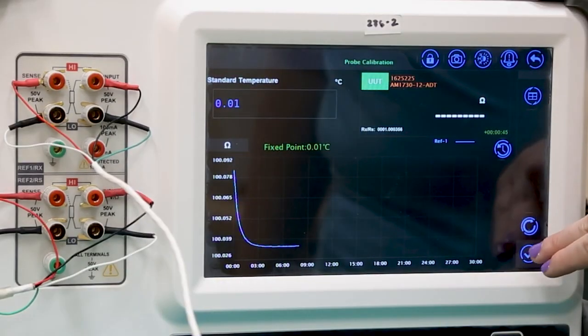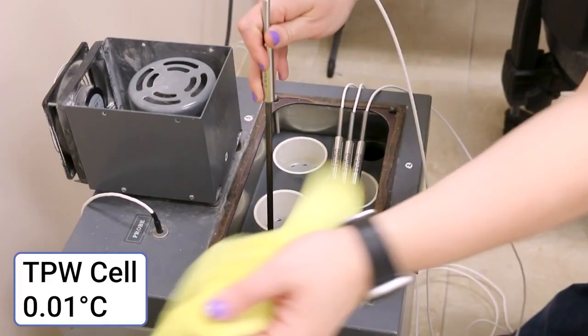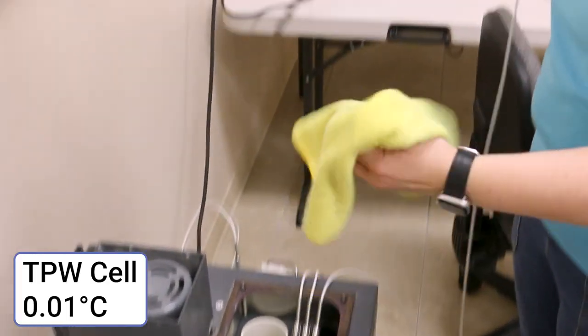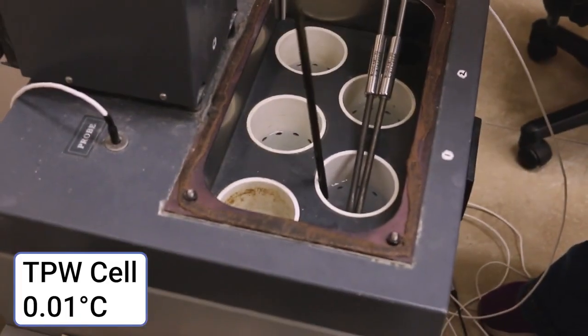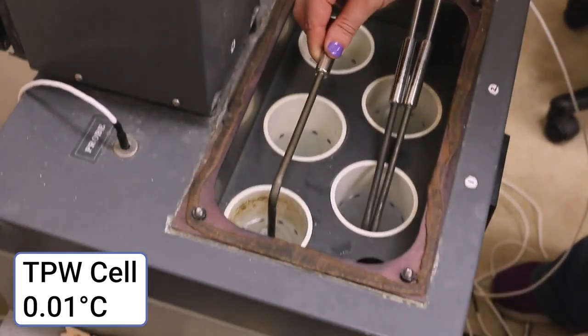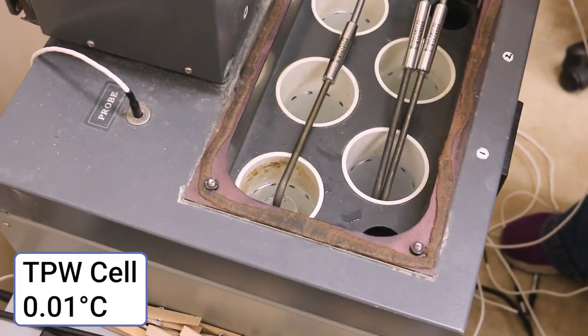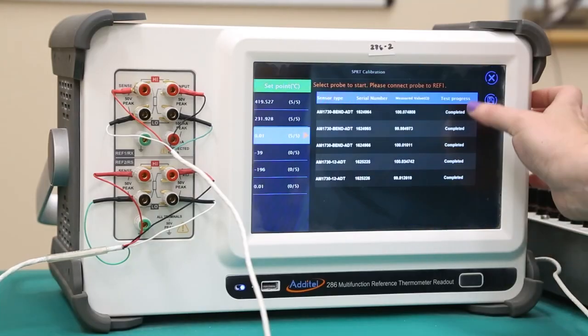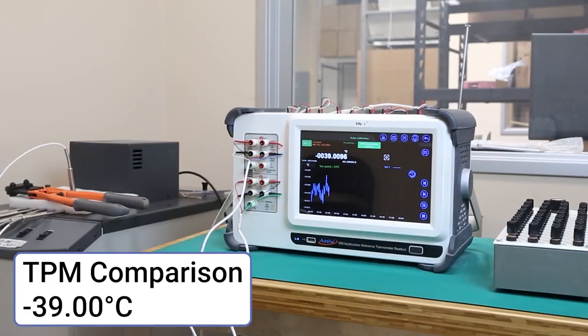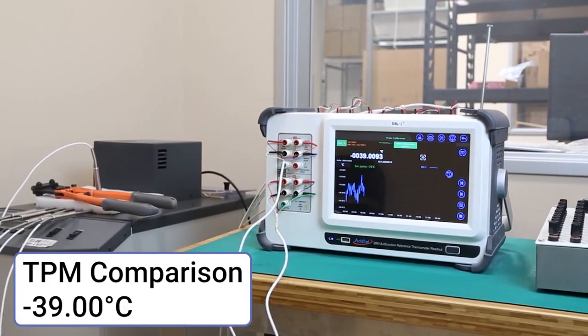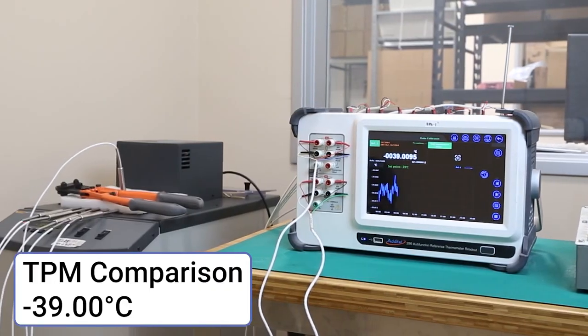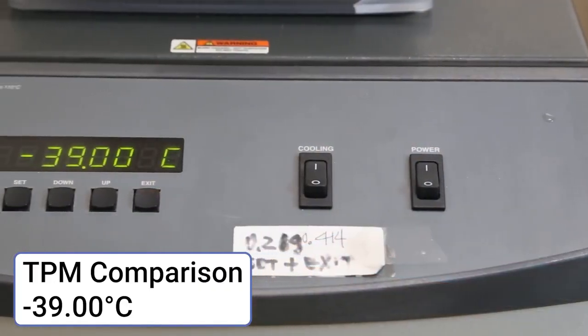After the probe has been measured, save the test cache, remove the probe from the cell, and dry it off. Swap the connection to the next probe to be measured, add it to the triple point cell, and repeat the process to complete the measurement. After all probes have been measured at the triple point of water, we will move to the triple point of mercury. Instead of a mercury cell, we will use a comparison calibration at -39 degrees Celsius.